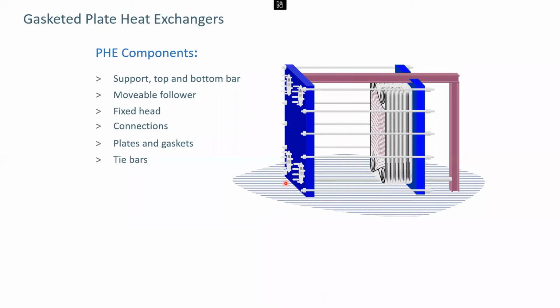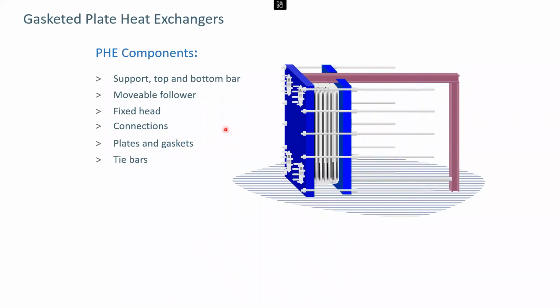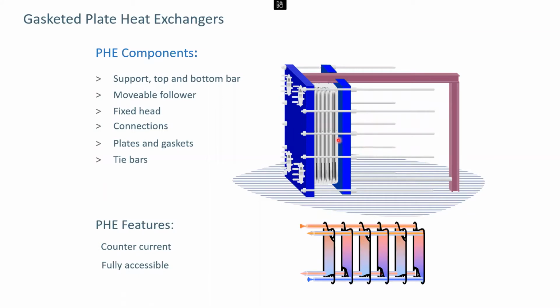So the tie bars go in, and we dimensionally close the heat exchanger so that these things are not closed by torque values or anything like that. They're closed by dimension, from the inside of the header to the inside of the follower. That's how they're closed, and it's all made up by the thickness of the plates themselves added to the thickness of the gaskets, multiplied by the number of plates. It's a dimension that should be very close, something like 1.5 to 2 centimeters between closed and not closed. Very standard.